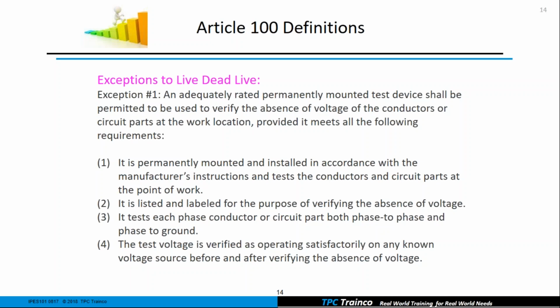So exception number 1, an adequately rated permanently mounted test device shall be permitted to be used to verify the absence of voltage. Okay, so that means that I do not have to have a qualified worker go into that piece of equipment and actually use a meter. I can permanently mount a test device in that equipment, and I'm going to show you a picture of this right after this slide, but we do have to meet some requirements, right?